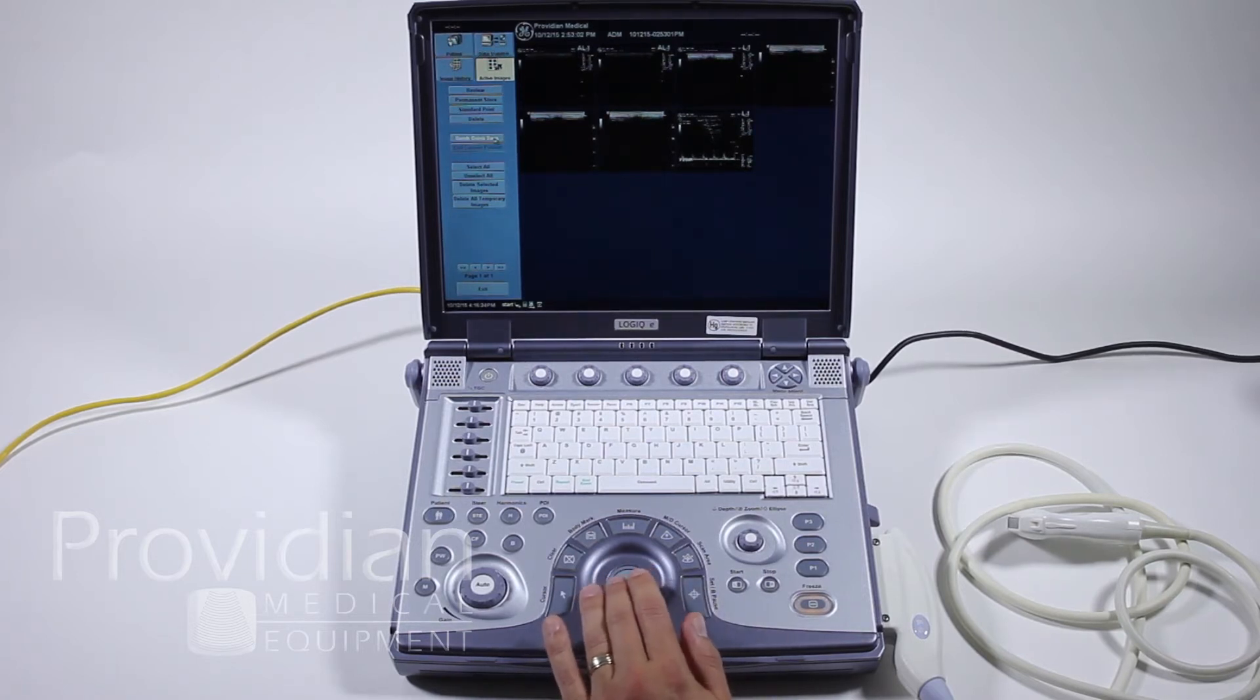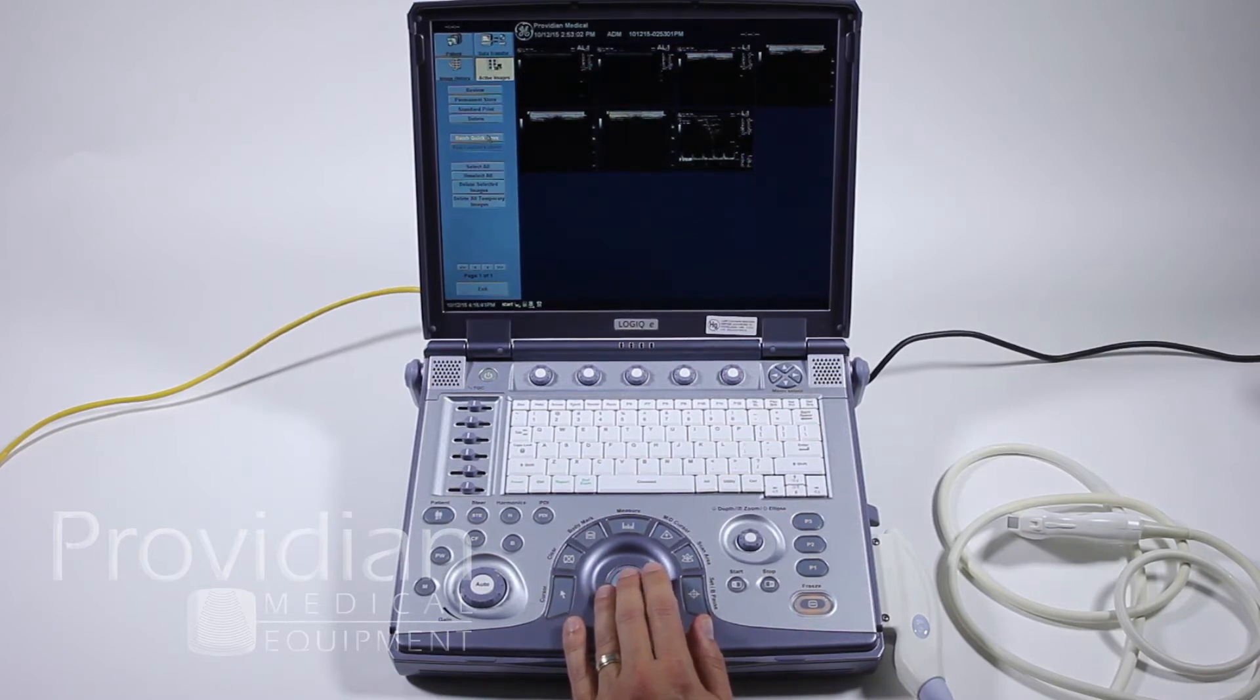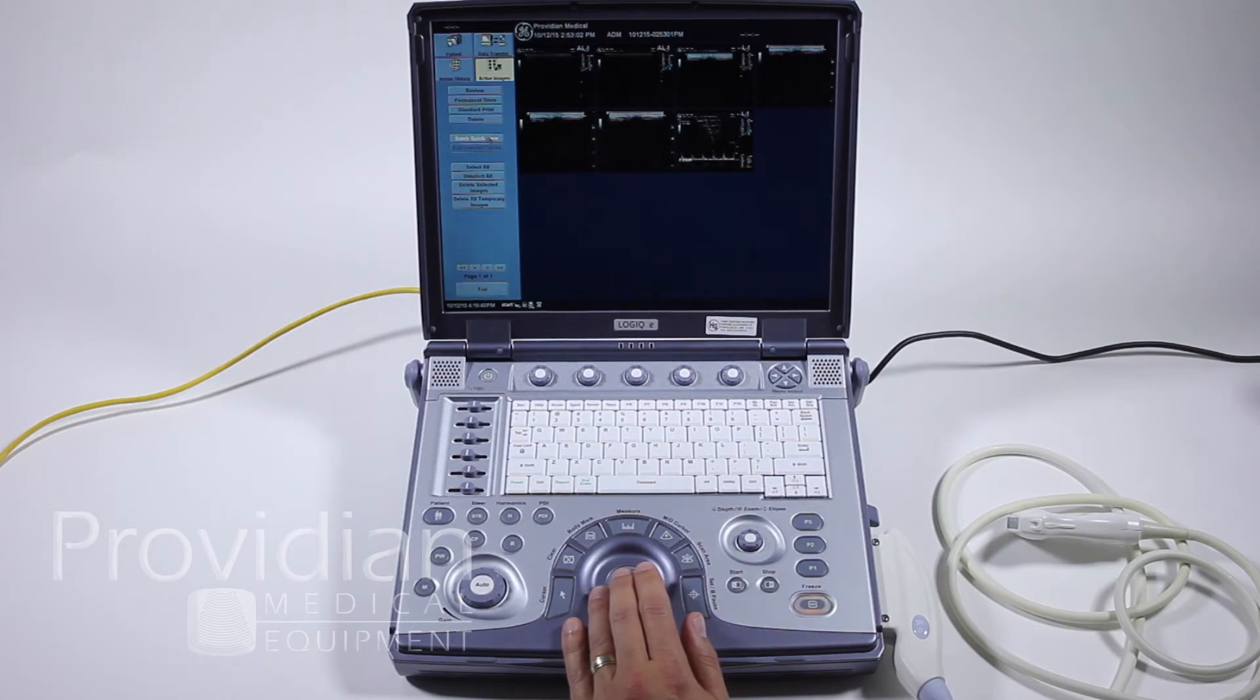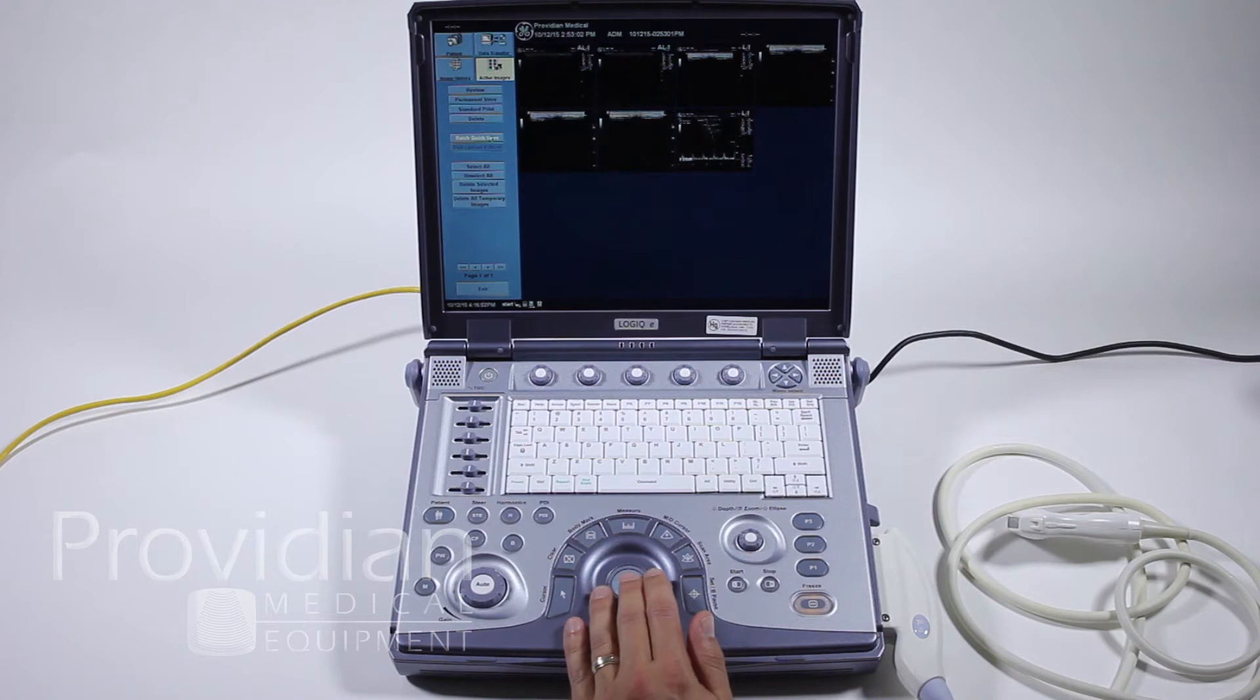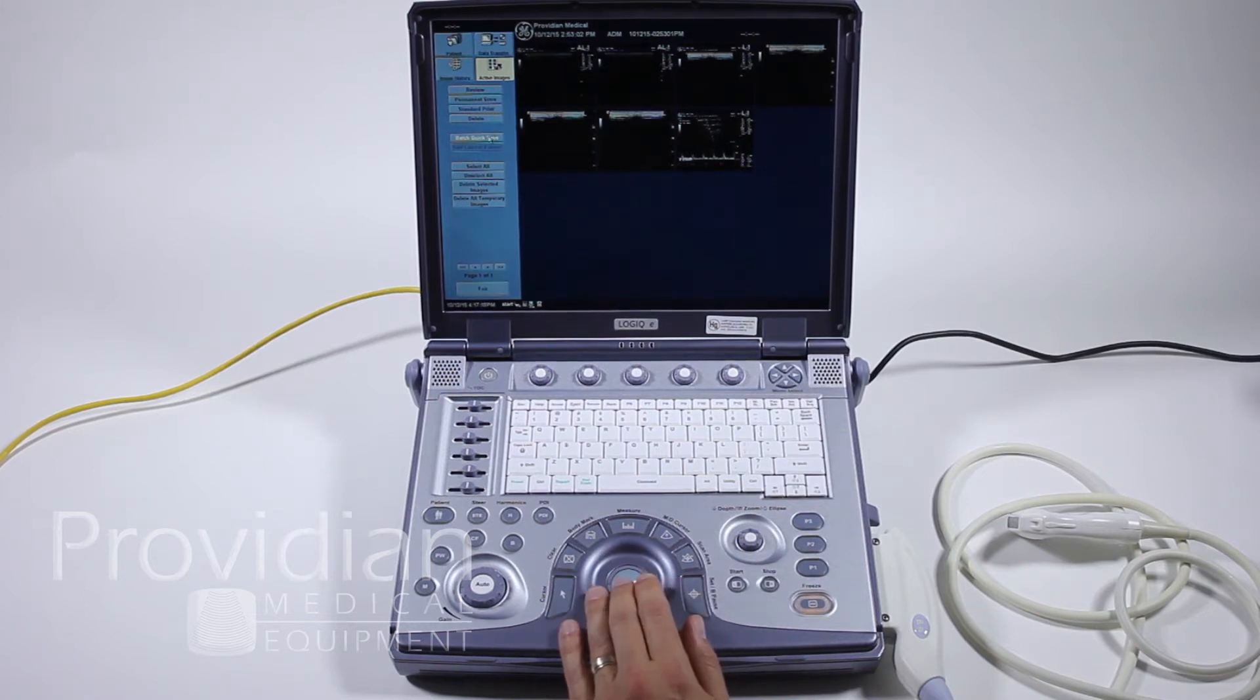First, there's a batch quick save here. This does allow you to save images to a USB stick. However, it's not always very helpful. I found that sometimes it exports the cine loops and images just fine, but other times the JPEG images did not come across. It's a very easy way to transfer images in JPEG or movie format, but I didn't find it to be always very helpful. Some of the JPEGs were corrupt, so I wouldn't trust it.